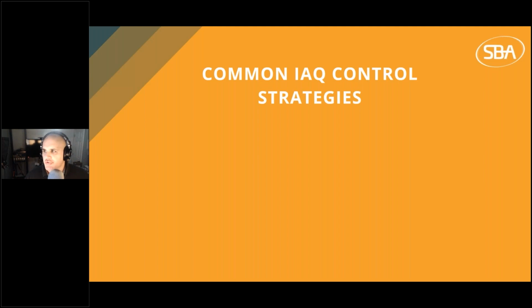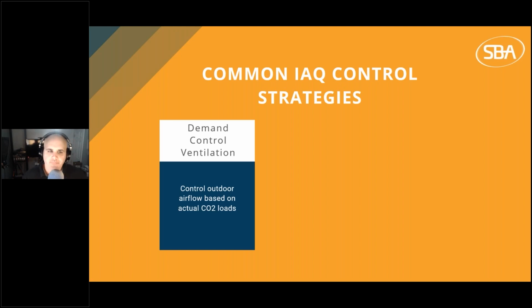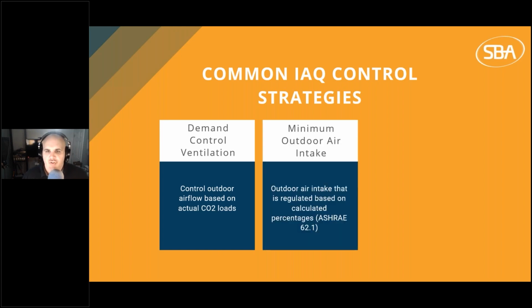Common IAQ control strategies. All right, let's take a look at these. The first of which is demand control ventilation. It's controlling outdoor airflow based on actual CO2 loads. There is minimum outdoor air intake, and this is basically what you're going to see in most buildings. ASHRAE is not recommending DCV right now because of the variability of outdoor airflow. But if you are having problems dealing with that enthalpy load being introduced by humid outdoor air, then they are recommending to step back to the ASHRAE 62.1 standards.